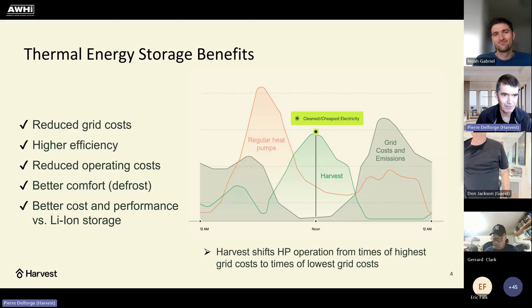So how do we do this? Thermal storage is often thought about with phase change material, or PCM, because they have high storage density. But we can also achieve high energy density with a water-based battery, sensible storage, versus latent storage. And the way to do this is to have a high temperature differential between charge and discharge temperatures. And in our thermal battery, we have about a 70-degree temperature delta between the hot water supply and the return from the heating element, from the air handler.